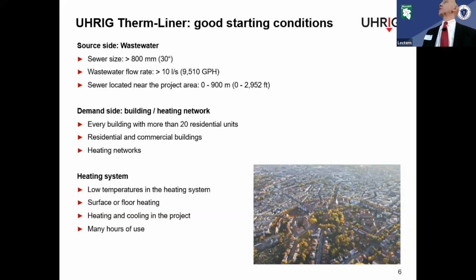Normally, we look for systems with pipes of 30 inches in diameter, with a minimum water flow of 10 liters per second. That resource, if you will, could be anywhere from really close to up to 3,000 feet away, because remember, we're just moving water or glycol through the loop, and we're providing that energy to the heat pump for use.